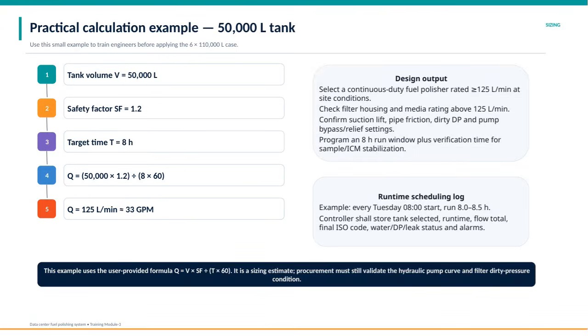Here, we're looking at a practical sizing example using a 50,000-liter tank. This smaller example is a great way to train engineers before moving on to the more complex case involving 6 tanks of 110,000 liters each. Let's go through the sizing steps. First, we start with the tank volume, which is 50,000 liters. Next, we apply a safety factor of 1.2 to ensure the system can handle slightly more than the nominal volume.